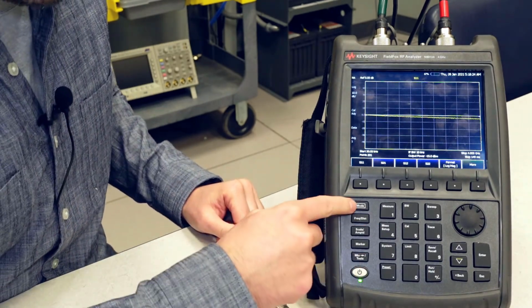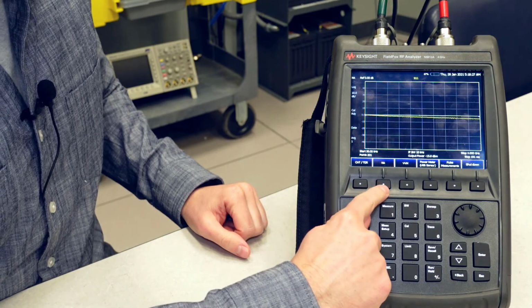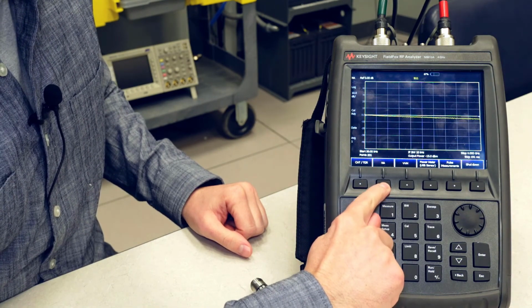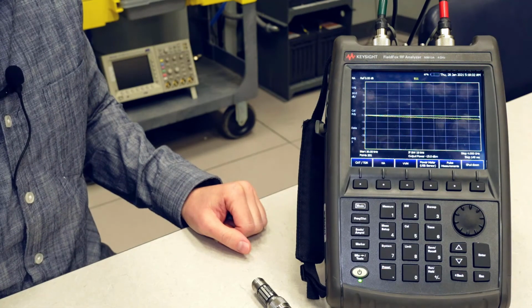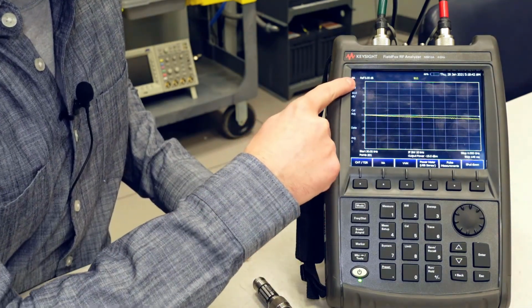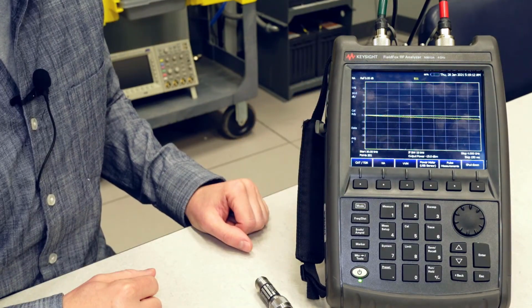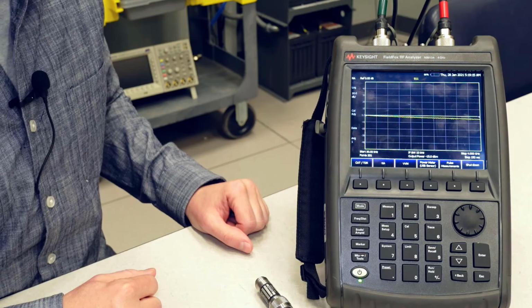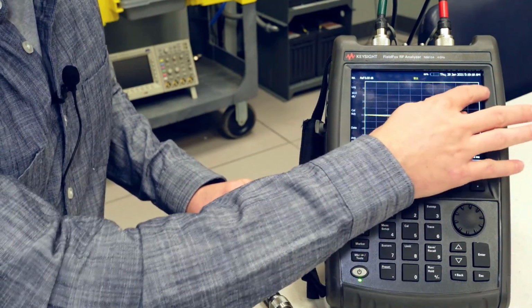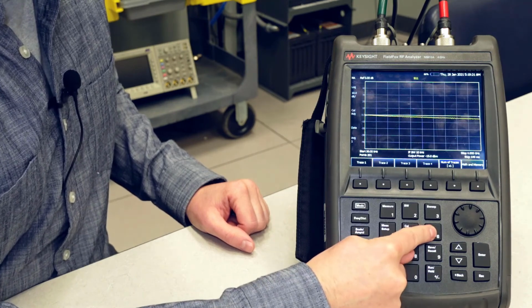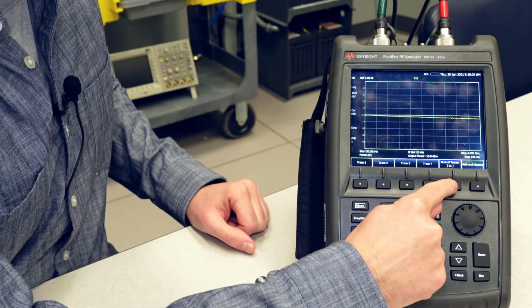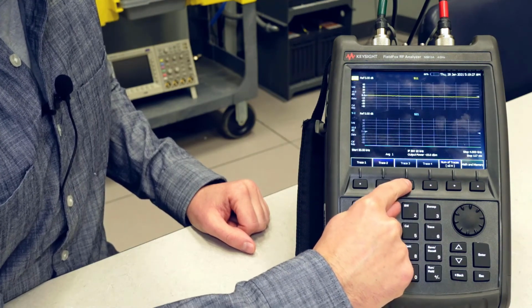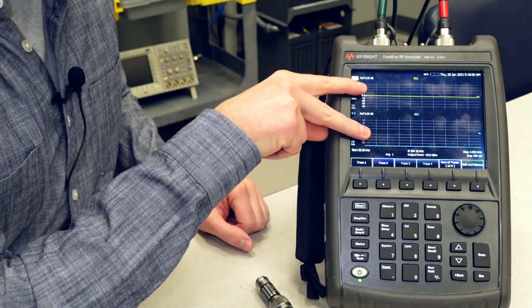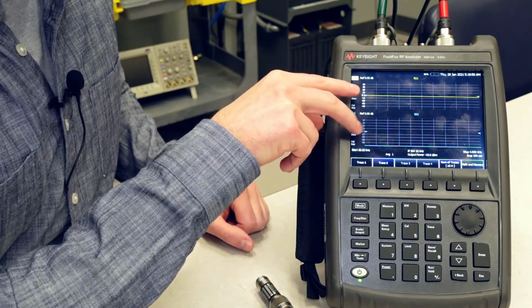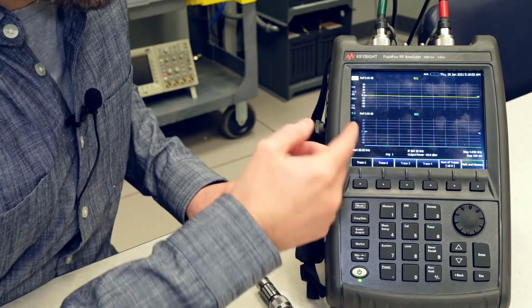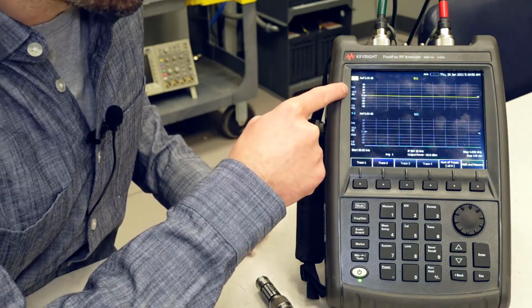So let's begin by selecting the mode function and then the soft key for Network Analyzer, or NA, to bring up the Network Analyzer mode. And we can confirm that up here in the top left by making sure that it says NA. Now to get started, we know that we first are wanting to look at amplitude and phase, so we should bring up two traces. Right now this is just one trace showing on the screen. If we hit number 6, trace key, and then number of traces, and select 2H, this is going to put now two traces, one above the other. So let's begin formatting trace 1 for amplitude. By default, it already comes up measuring in dB, or logarithmic magnitude.